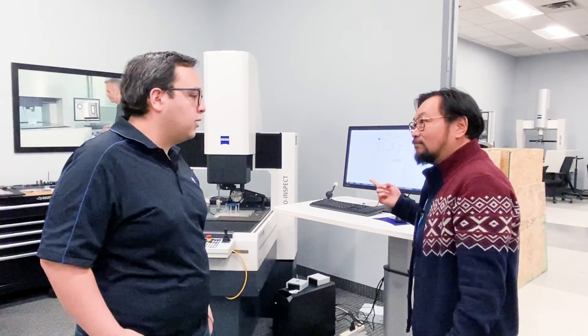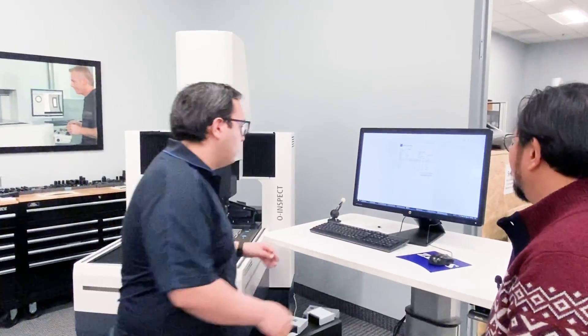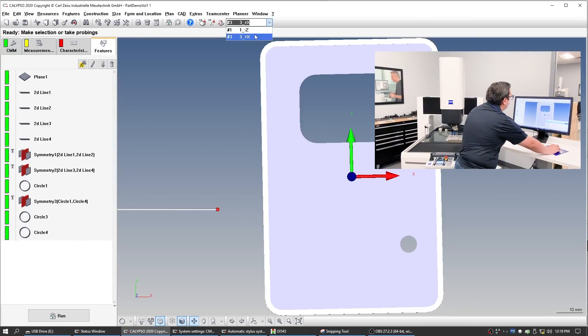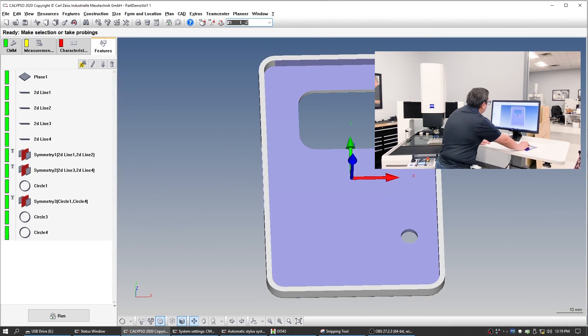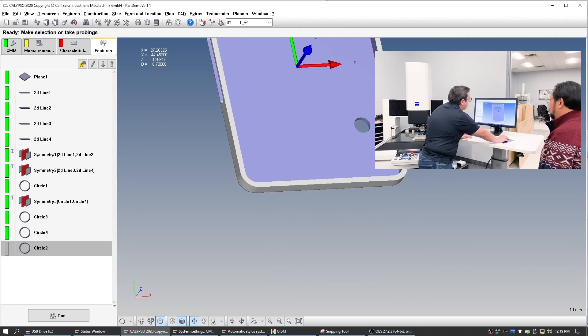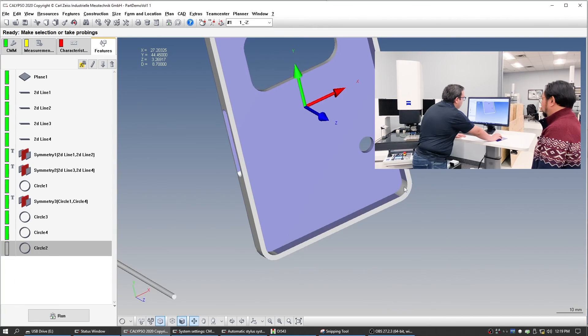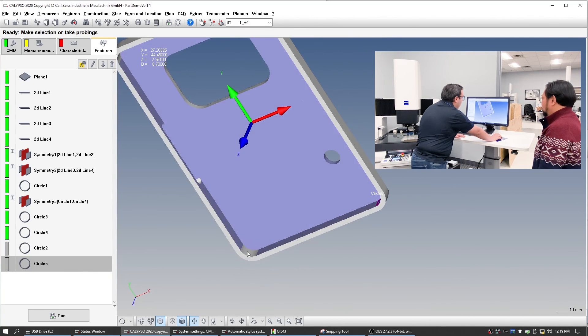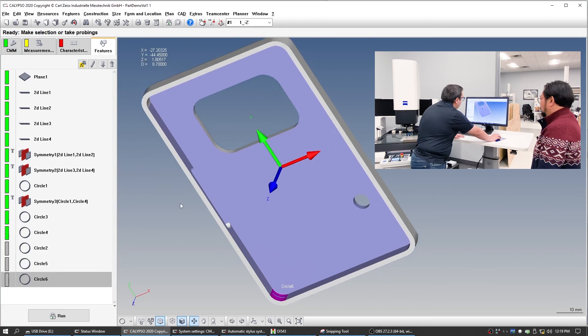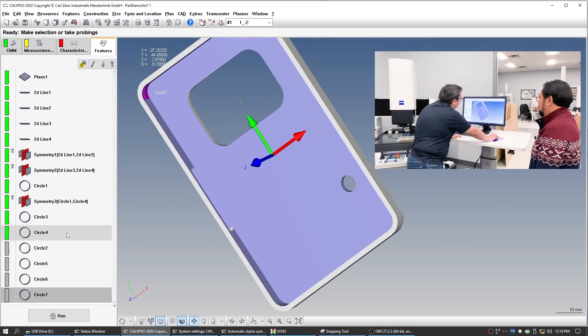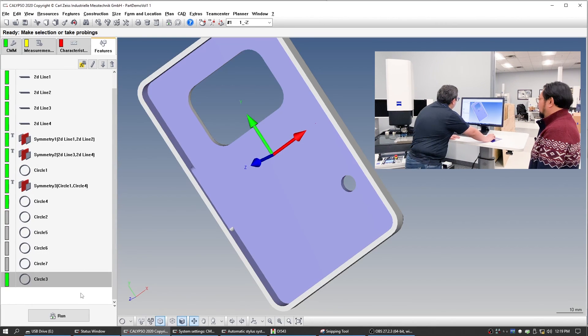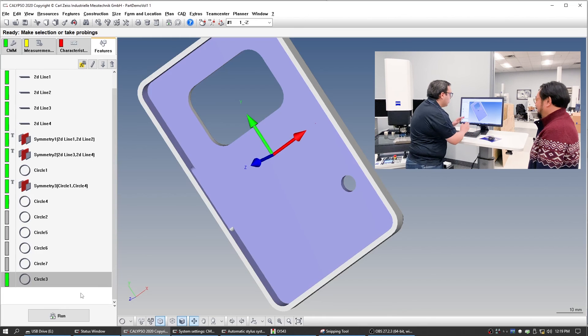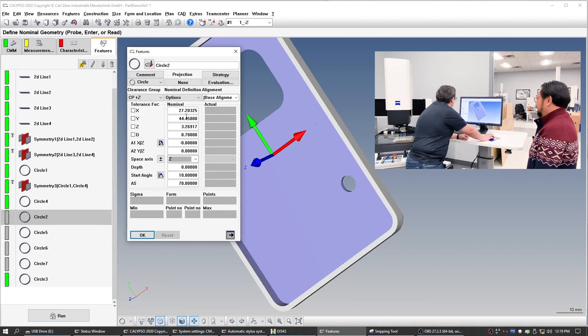The stylus is in there, so we should be able to do that right now. Cool, yeah. Can we do it? Yeah, let's do it! Let's make sure that we're doing it with the one that's straight down — the 1_minus_Z. Then what we have to do from here is select the radii. Let's go clockwise. The only thing I'll do is make sure that they are measured at the same height, that their clearance plane is correct, and then we should be good to go. Let me actually move circle three down to the bottom — this will make it run smoothly through the whole thing. Clearance plane plus Z. It's done at this height. It changed from when we originally programmed it, only because we now have a base alignment.